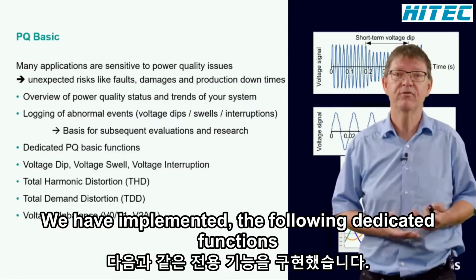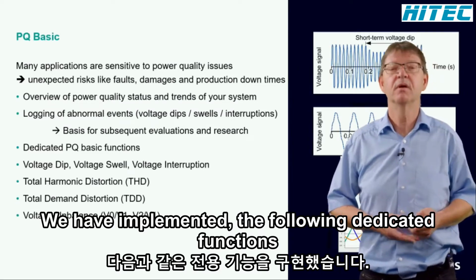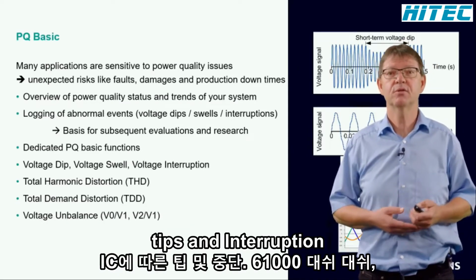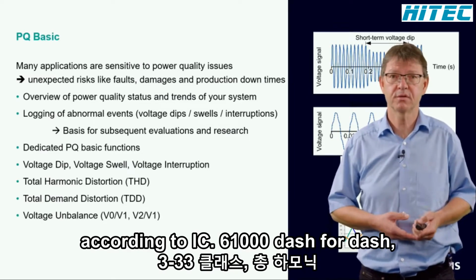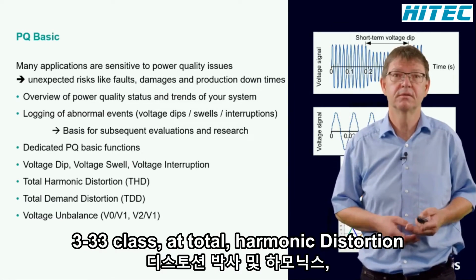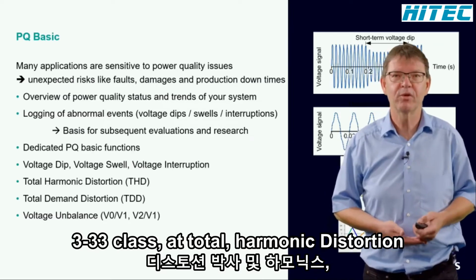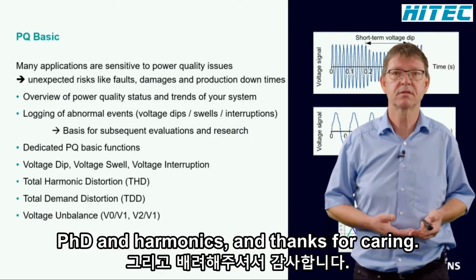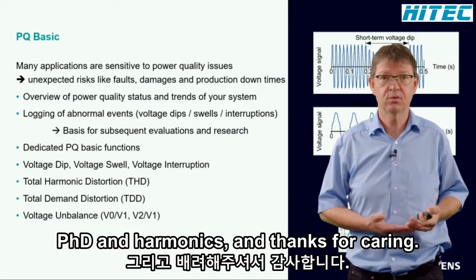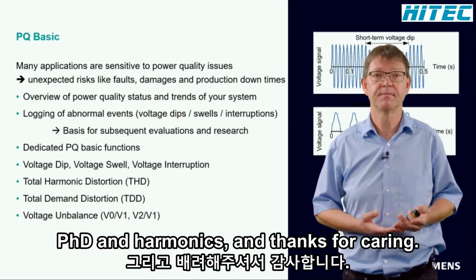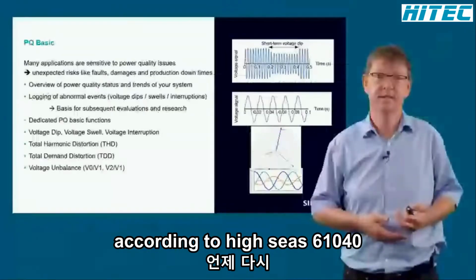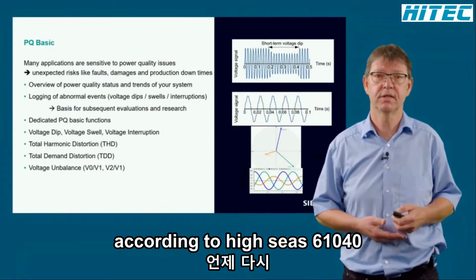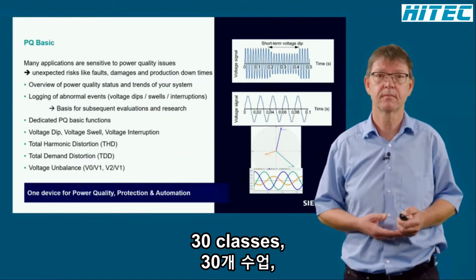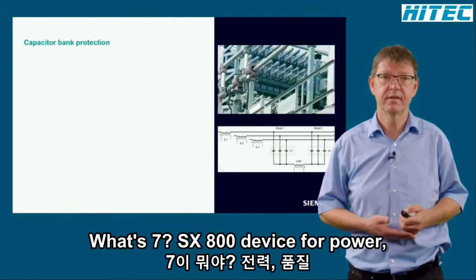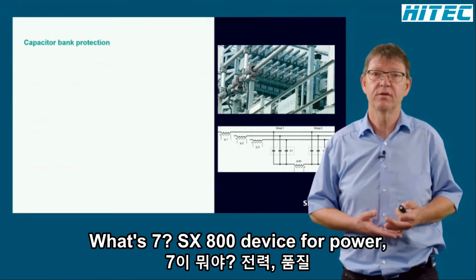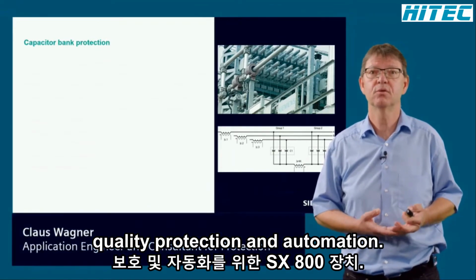We have implemented the following dedicated functions: voltage dips, swell, and interruption according to IEC 61000-4-30, class S, total harmonic distortion THD, and harmonics for voltage, total demand distortion TDD, and harmonics for currents. Voltage unbalance, again according to IEC 61000-4-30, class S. With 7SX800, you get one device for power quality, protection, and automation.